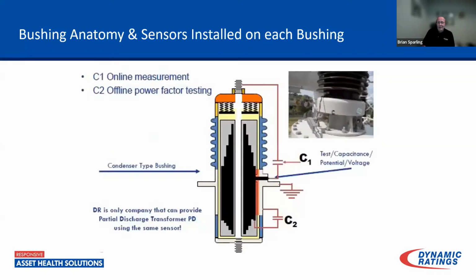So there is a way to detect these failure conditions. So long as the bushing has the test tap, or the C1 test tap, available, we're able to utilize that and install a sensor onto all 3 phases of the bushing. From that, we measure the C1 leakage current of the bushing in operation. The lead is then brought down into a monitor where we do measurements and a bunch of calculations to derive when things are normal and, more importantly, when things become abnormal.